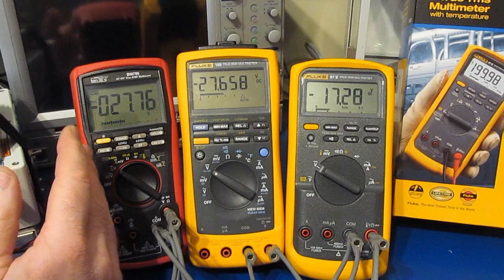You can see the Fluke displaying 38. Right there it just switched over, and you can see now it's reading correct at 100.6 volts, basically the same value the other meters read. I would imagine if we take up the voltage now, it's going to be accurate. It's 406 on all three meters.